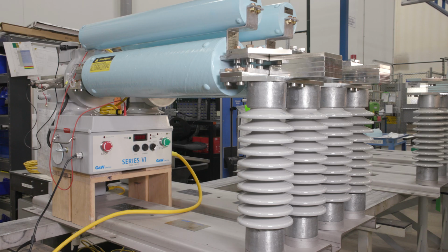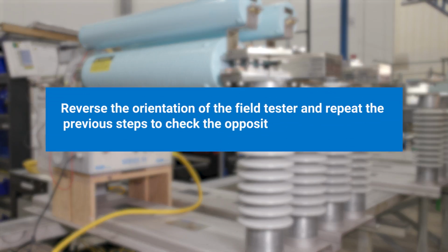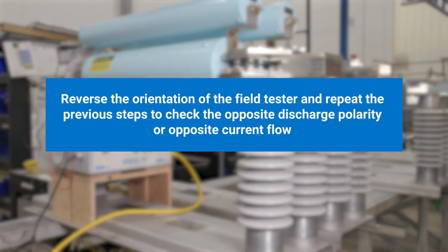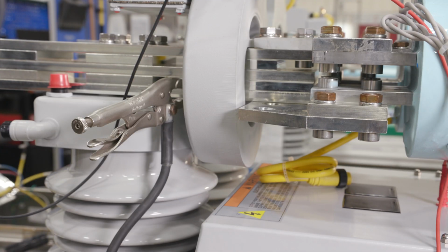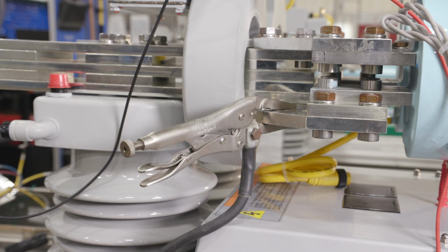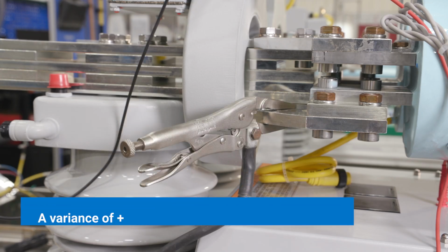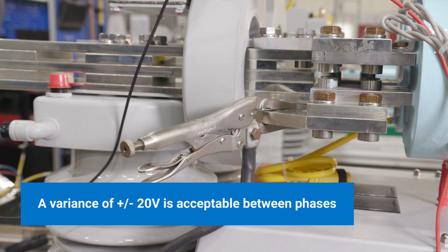Since the CLiP current limiting protector is a bidirectional device, reverse the orientation of the field tester and repeat the previous steps to check the opposite discharge polarity or opposite current flow. Do this by flipping locations of the vice grip pliers. Record the voltage at which the SFL is fired for all phases and directions. A variance of plus or minus 20 volts is acceptable between phases.